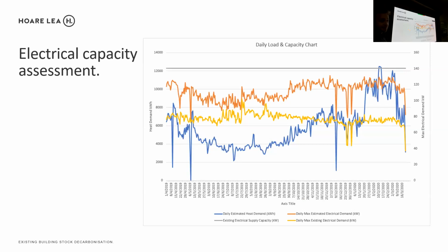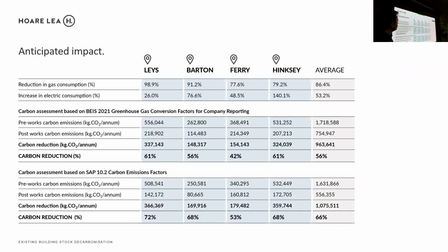Because we had the electrical data half-hourly, we could map in our, the orange yellow line is the before, the electrical consumption, and the red line is the after the heat pump installation. And the grey line at the top is the agreed peak maximum capacity that the site in question had. So we could prove that we weren't going to trigger the requirement for an electrical supply upgrade. I'll come back onto that in a minute.